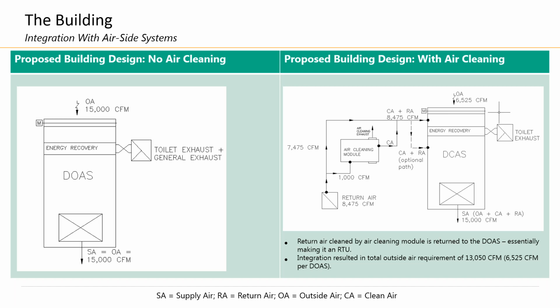Off to the right here, you've got return air, which you would pull from the general exhaust. So the general exhaust becomes a return now, essentially. The air cleaning modules will scrub a portion of that return and then put that air back into that clean air and return air back into what we call a DCAS, a dedicated clean air system. That enables you to reduce outside air from that 15,000 number down to 6,500 CFM. Energy recovery can now be completely eliminated or greatly reduced because it's only treating the toilet exhaust. And supply air remains constant so that you can still take advantage of economizer mode. A very much more efficient way of designing here.